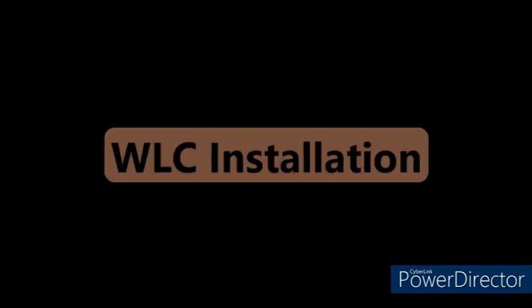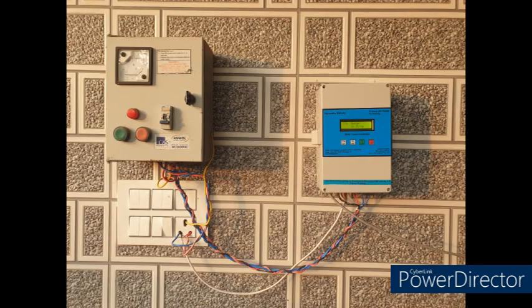Warning. Both WLC panel and feeder panel must be in power off condition until specifically asked to turn on the power of either of the panels. WLC panel installation. WLC panel is wall mounted. Identify a clean, shaded area with proper ventilation and no water ingress, near to the pump feeder panel but at least 300 mm distance.